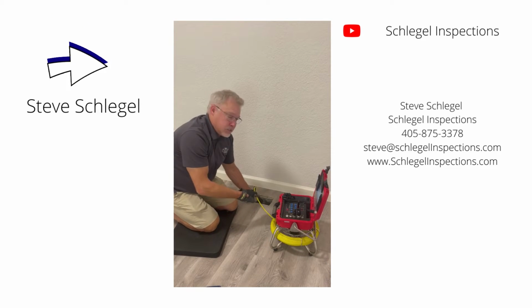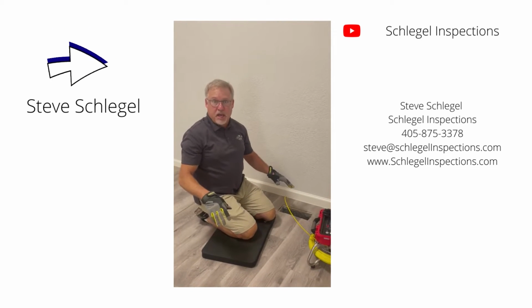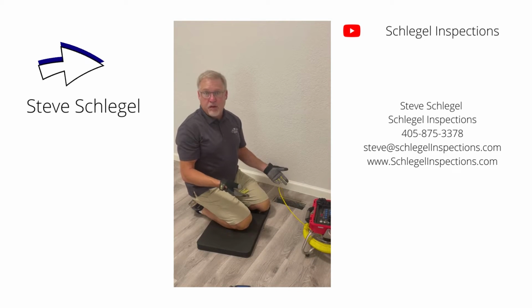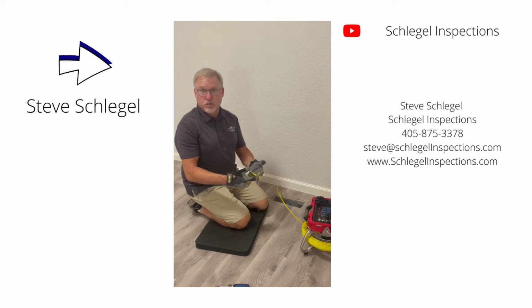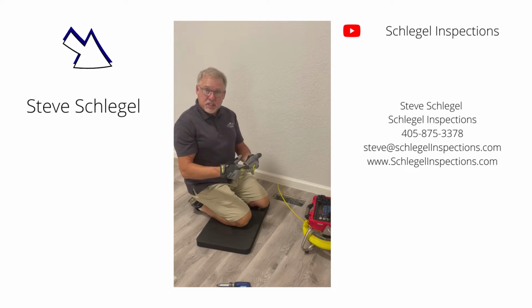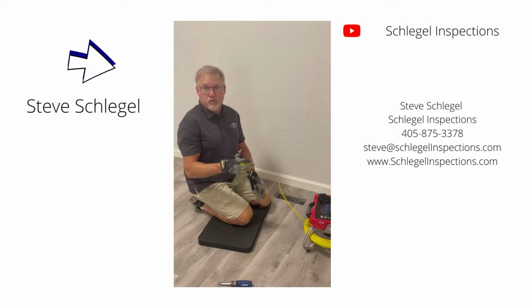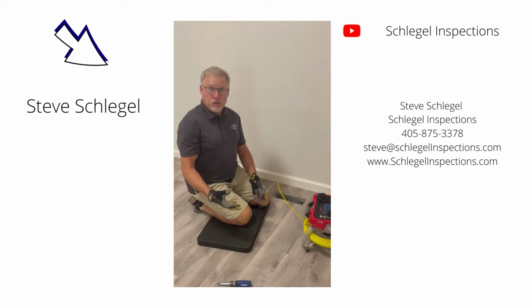Well, in this particular case, this house was built in 1989. The ductwork is in the slab, and that's where our concern is. One, the age, so we're now about 33 years old. In this case, it's galvanized steel, and it's gonna be exposed to moisture that potentially could come from the foundation, and corrosion, offsetting of the joints, sand will enter into the ductwork. It can end up being a health hazard in many cases if there's significant moisture intrusion. And so we wanna just make sure that the integrity of the ducts are good at this point.